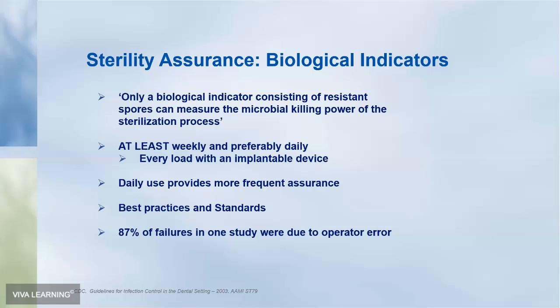In our setting, implantable device here does not mean a dental implant. Those are sterile, typically in a double vial and gamma irradiated before they arrive in the office. In fact, if you were to place them in an autoclave, if it's in the vial, it won't do any good. And in fact, the implants can actually be damaged by autoclaving. So it's not referring to implantable devices. So anyway, preferably daily, certainly at least weekly. If you think about it, daily use provides more frequent assurance, which also gives peace of mind. And I would expect, particularly given the current situation, we'd want to know for the load that in fact sterility was assured.